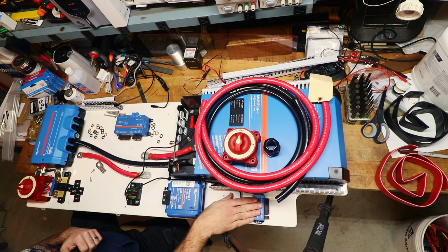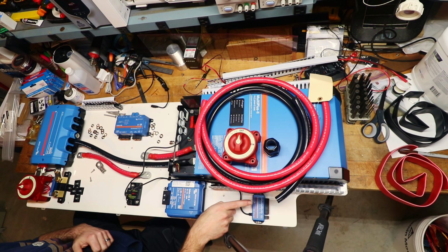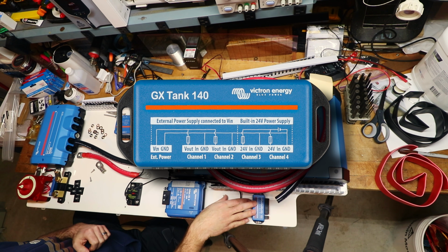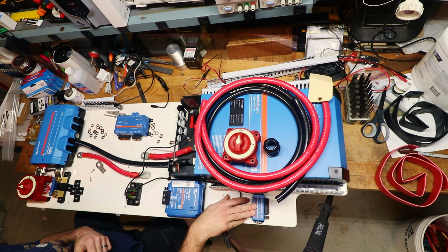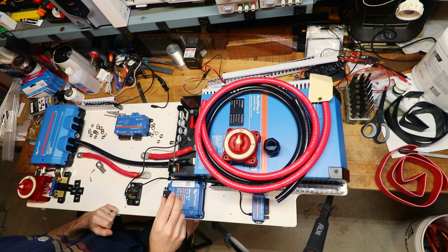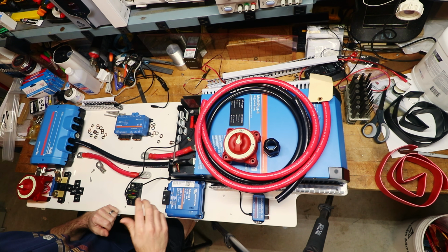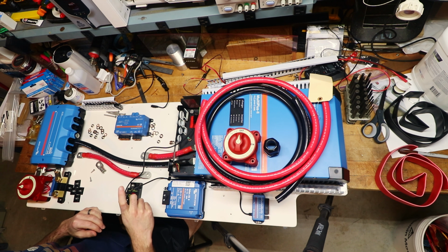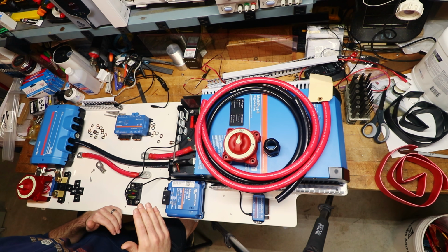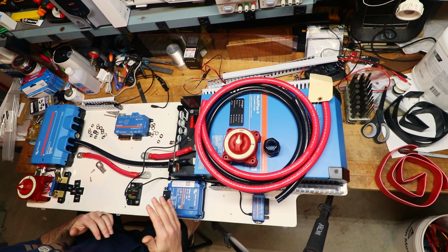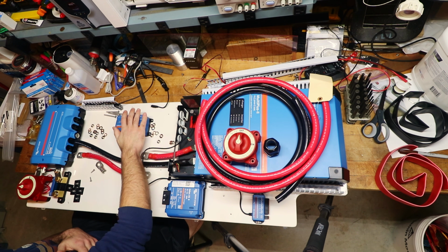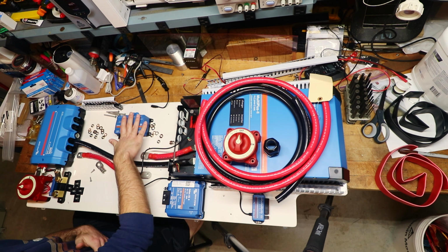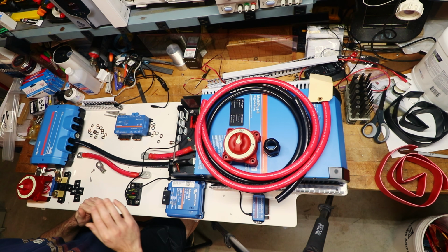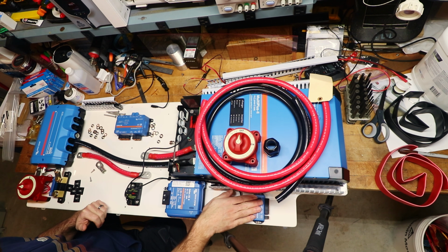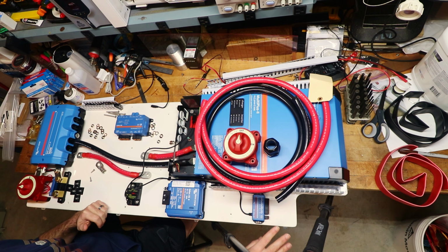The one other thing over here that we didn't talk about is the GX Tank 140. A lot of people won't have any need for this. The reason I do is if you remember back to the video where I was working on the plumbing, we put a pressure transducer in the water tank under the aft cabin floor. That pressure transducer works on a 4 to 20 milliamp scale, and that's how it integrates with the inputs and output, or the I/O, of the Cerbo GX. The Cerbo GX does not directly have the ability to read a 4 to 20 milliamp circuit, so in order to do that, you need this additional component that can provide the correct power to those types of sensors.